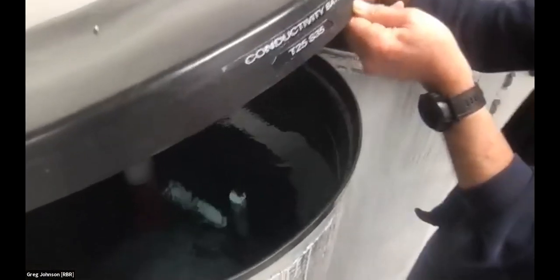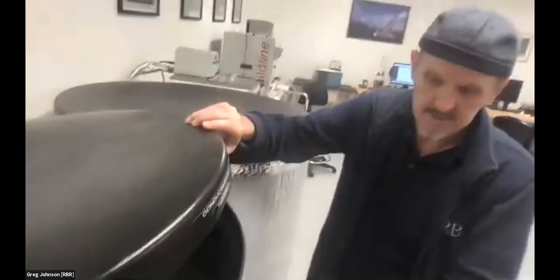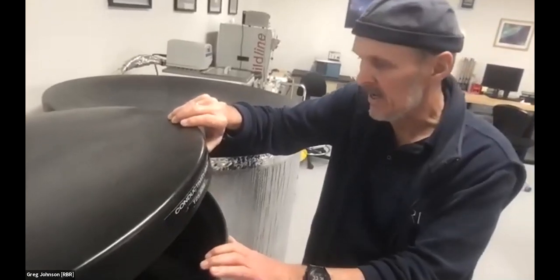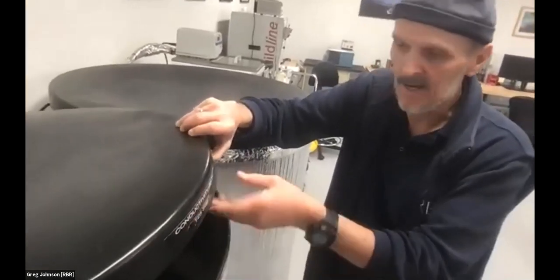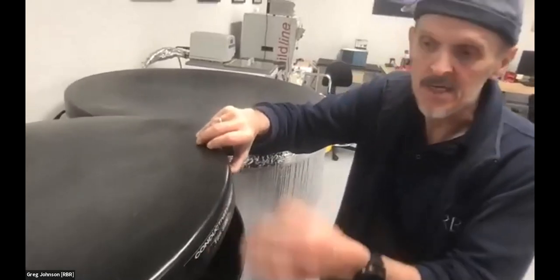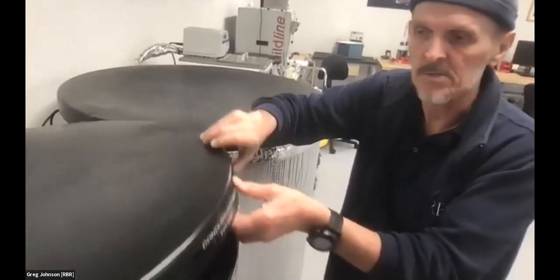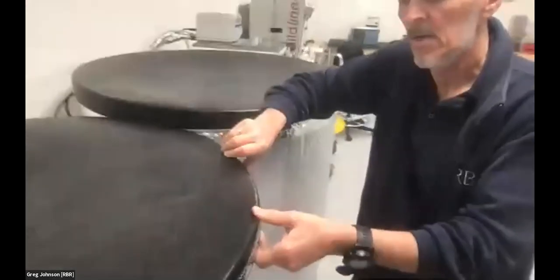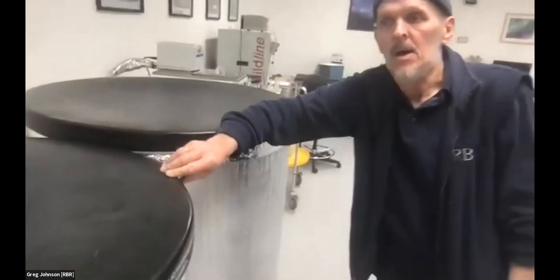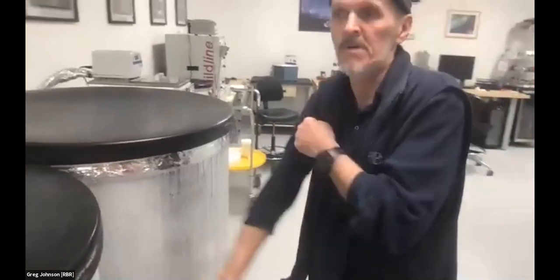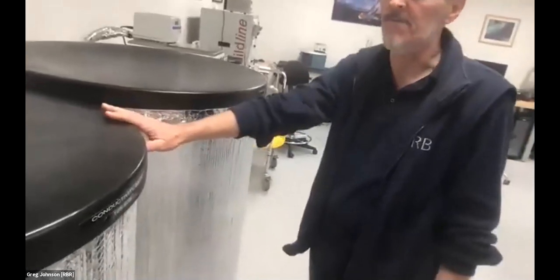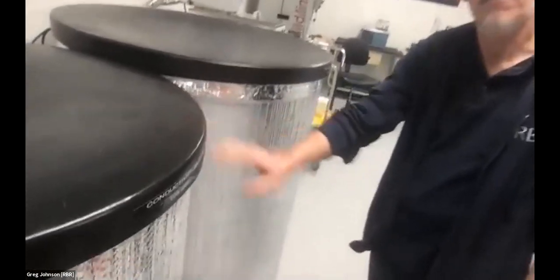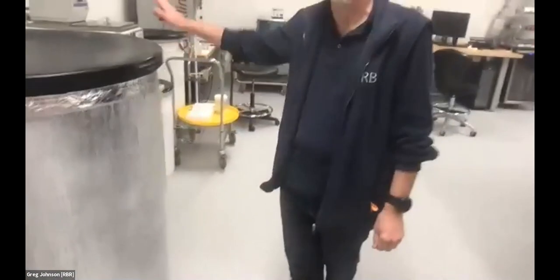And the second one doesn't seem to have a double jacket. Yeah, so it's set to balance with room temperature, with only having internal submersible pump heat and just eventual balance with room temperature. So what's the temperature in our lab here? So now it's 22.5 degrees. All right. It makes about 24 degrees in that part. So that submersible pump that's used to stir the water adds a couple of degrees, which is why we're sitting closer to 25.